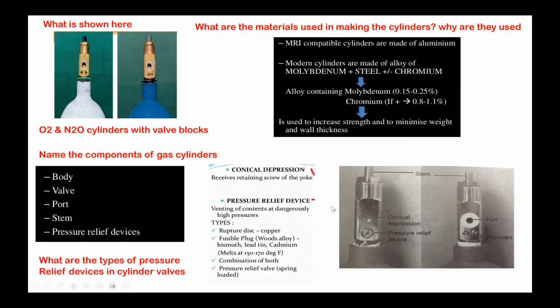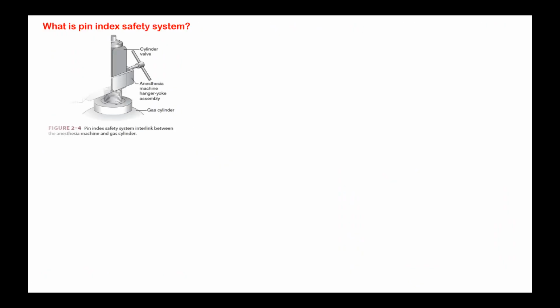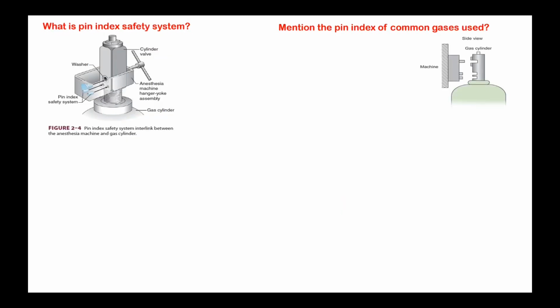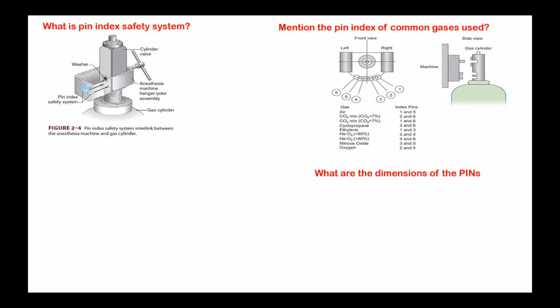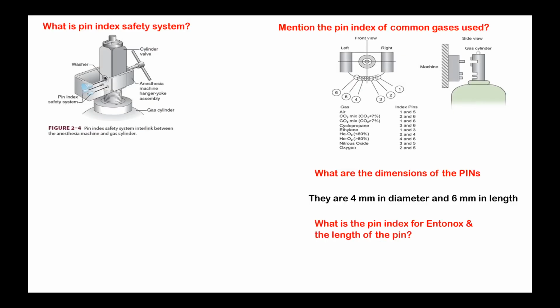So this is the same picture I showed you earlier. Pin index safety system. What is the purpose of the pin index safety system? It is gas specific. It prevents faulty connection, the wrong mounting of a gas. Okay? So the oxygen hanger yoke assembly will not accept a nitrous oxide cylinder or an air cylinder. So this is to prevent the wrong mounting of the cylinders or gases. That is the answer that you have to give.